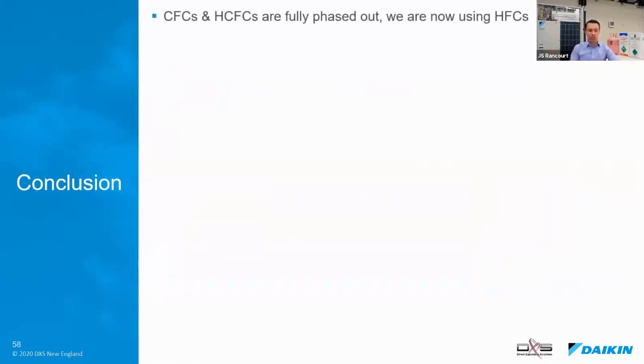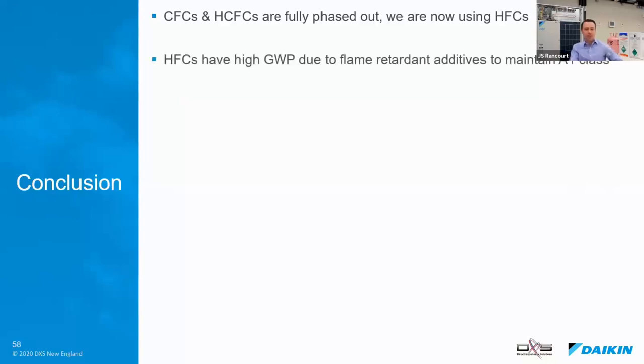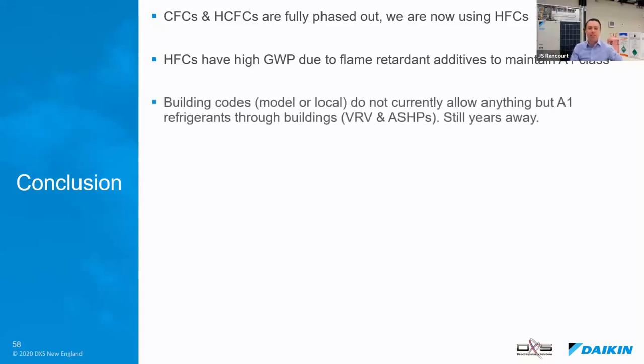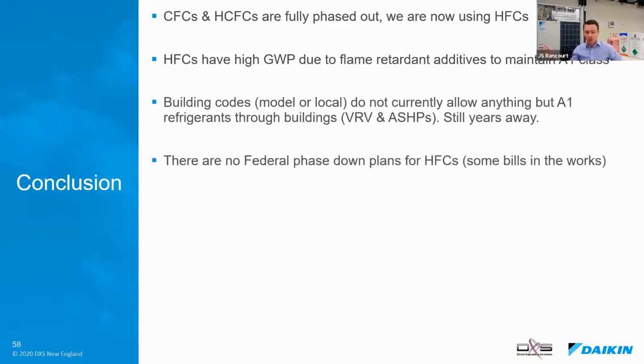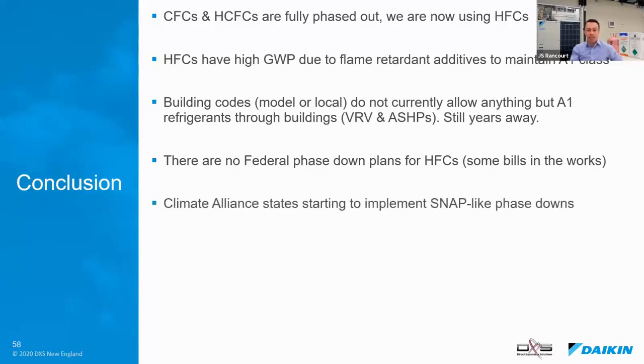Quick conclusion here to try and cover everything I talked about in one slide, so you're not as confused as Ricky at the bottom, at the beginning of my presentation here. CFCs and HCFCs are out. HFCs have high GWP due to the flame retardant additives that we put in it. Building codes don't allow anything but A1s inside the building, and we're still years away. There's no federal phase down of HFCs, but some stuff's in the works. The Climate Alliance states are starting to implement SNAP-like phase downs. Is SNAP-like a word? I don't know, I made it up.